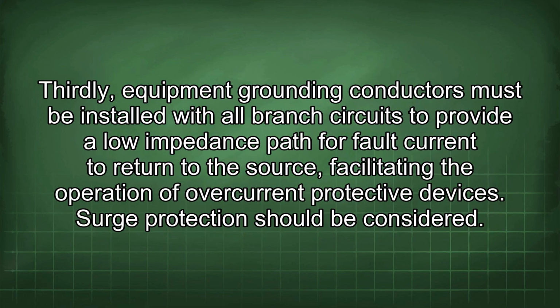Thirdly, equipment grounding conductors must be installed with all branch circuits to provide a low impedance path for fault current to return to the source, facilitating the operation of overcurrent protective devices.